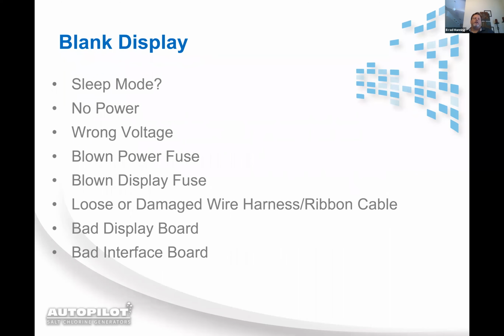A blank display on a Pool Pilot Professional, you've either got a blown display fuse or a blown power fuse. The power fuse is going to be up there by the transformer on the backside of the hydraulic circuit breaker. Or you've got the wrong incoming voltage. The AutoPilot Professional comes out of the factory at 220, and there is no conversion for it. It is to run off of 220. So you might not have a display if you've got it on a double pole breaker and one of the legs has dropped out.